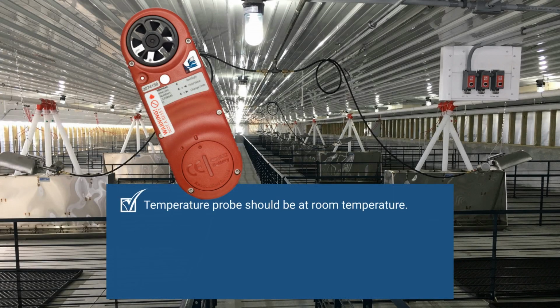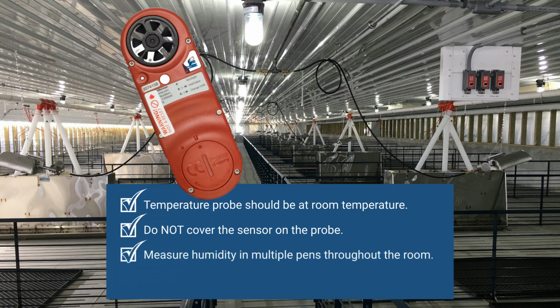To begin measuring humidity, be sure the humidity probe has had time to reach room temperature so the measurement is not skewed. Do not cover the sensor on the probe. Be cautious of where the probe measures humidity. Once the probe is acclimated to the room, it is recommended to check humidity in multiple pens throughout the room. Avoid measuring too close to inlets and heaters.